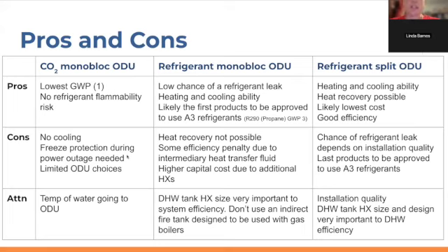And then, as I said earlier, Europe already in some areas approves the use of propane, which has an even lower global warming potential than R32 and 454B. Propane only has a global warming potential of 3, but it's highly flammable. So here in the US, it's still not allowed, but in Europe, some parts do allow it. If it starts being allowed here in the US, then I'm sure they would follow the path that Europe is taking, which is that they only allow propane to exist in outdoor unit equipment that is monoblock style, so that no propane refrigerant is being piped inside the home. So it's likely that here in the U.S., those monoblock style outdoor units with propane will be the first to be approved.